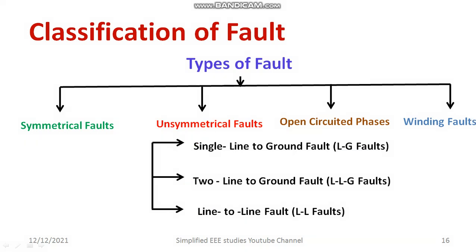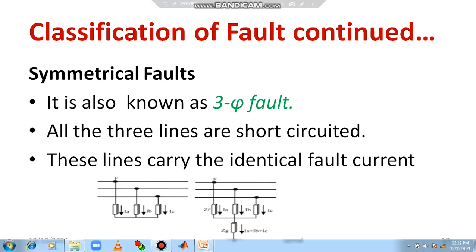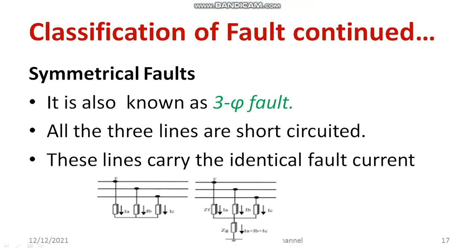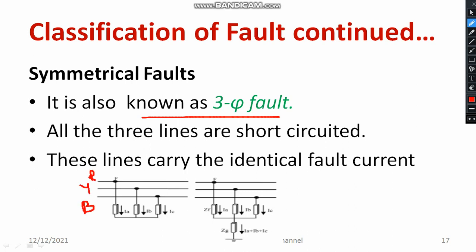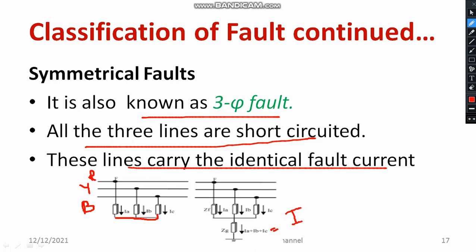Let me discuss the meaning of symmetrical fault. You know the word meaning of symmetry — suppose there is a box; if you cut it in a particular plane it should be divided equally. In case of symmetrical fault, it is also known as three phase fault, applicable for the three phase system. Consider a three phase system with R, Y, and B lines — the three lines are short circuited. Thereby equal current flows through each line, and the fault currents are divided equally. The total fault current is IA plus IB plus IC, and the magnitude is very high. Among all types of fault, symmetrical fault carries the highest magnitude of fault current.